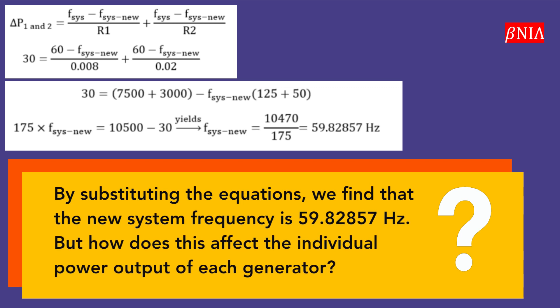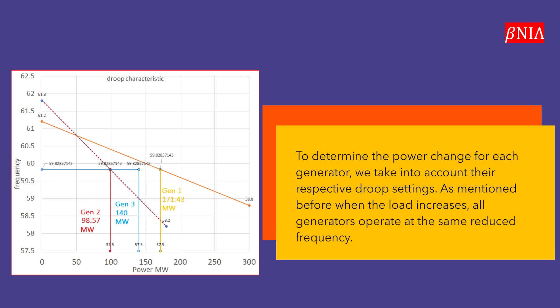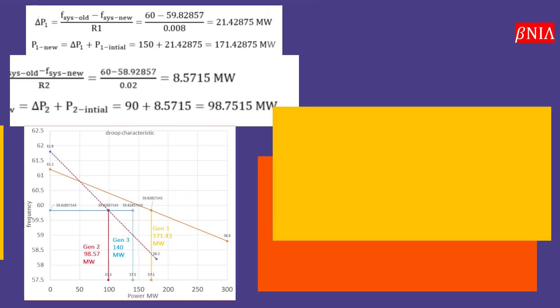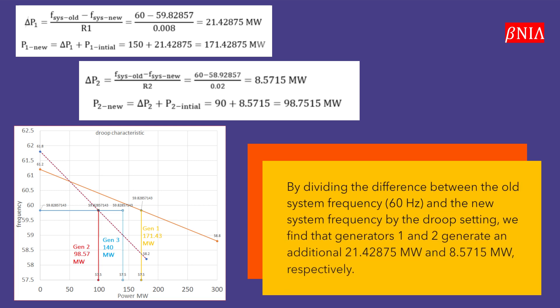But how does this affect the individual power output of each generator? To determine the power change for each generator, we take into account their respective droop settings. As mentioned, when the load increases, all generators operate at the same reduced frequency. By dividing the difference between the old system frequency of 60 Hz and the new system frequency by the droop setting, we find that generators 1 and 2 generate an additional 21.42875 MW and 8.5715 MW, respectively.